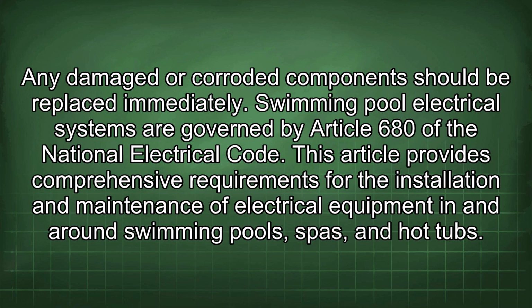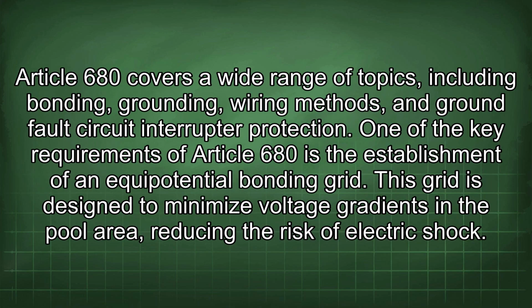Swimming pool electrical systems are governed by Article 680 of the National Electrical Code. This article provides comprehensive requirements for the installation and maintenance of electrical equipment in and around swimming pools, spas, and hot tubs. Article 680 covers a wide range of topics, including bonding, grounding, wiring methods, and ground fault circuit interrupter protection. One of the key requirements of Article 680 is the establishment of an equipotential bonding grid. This grid is designed to minimize voltage gradients in the pool area, reducing the risk of electric shock.